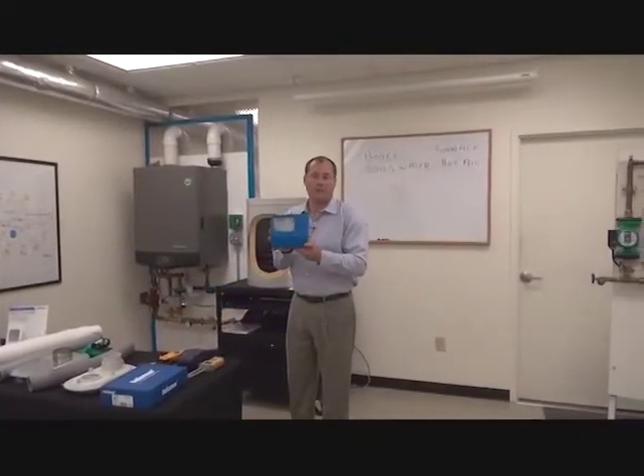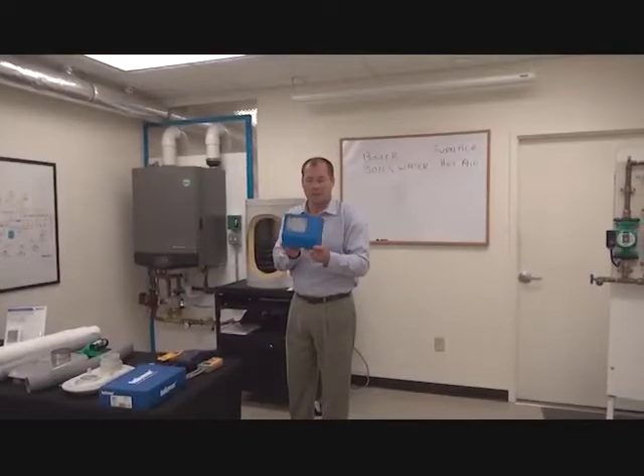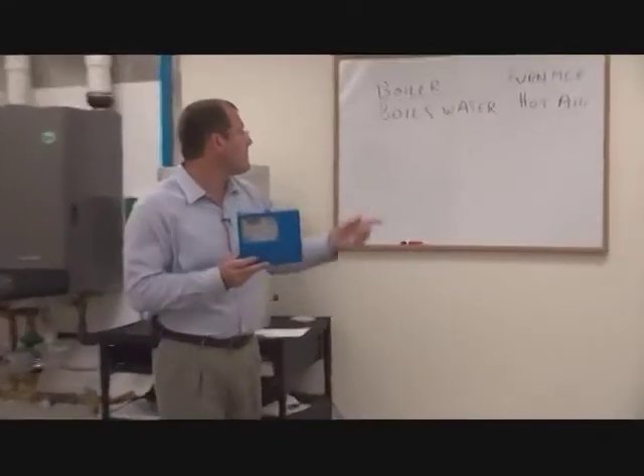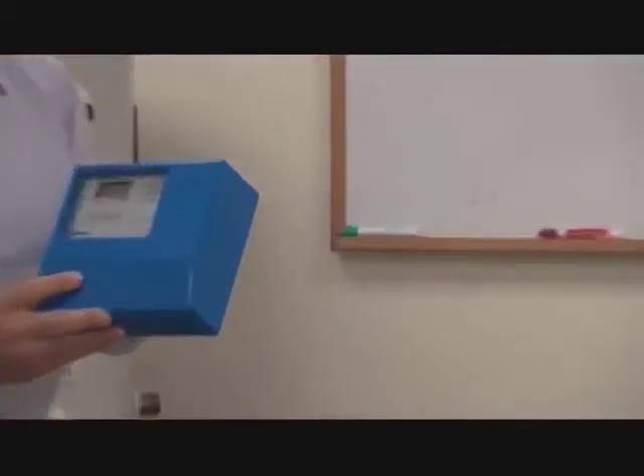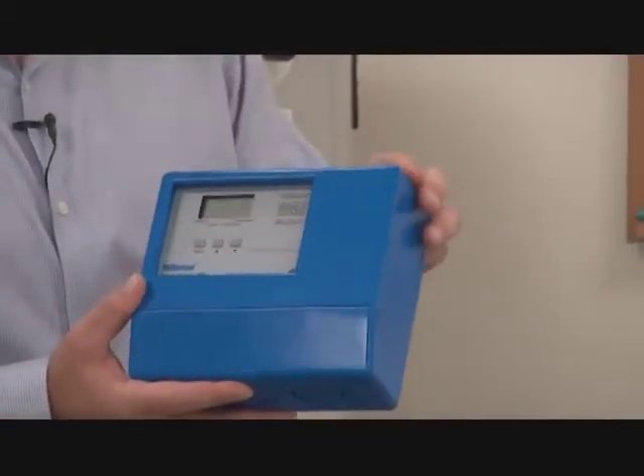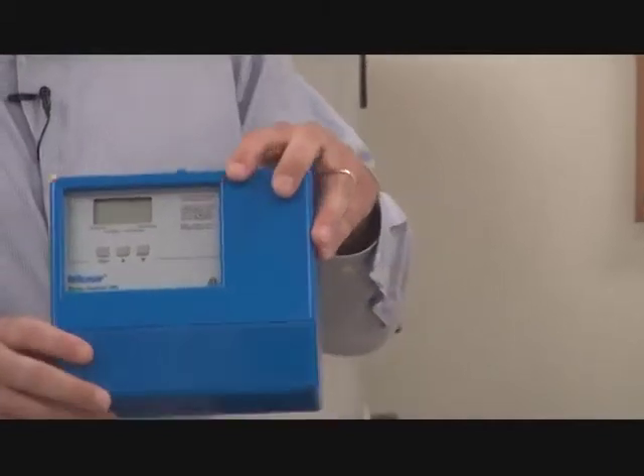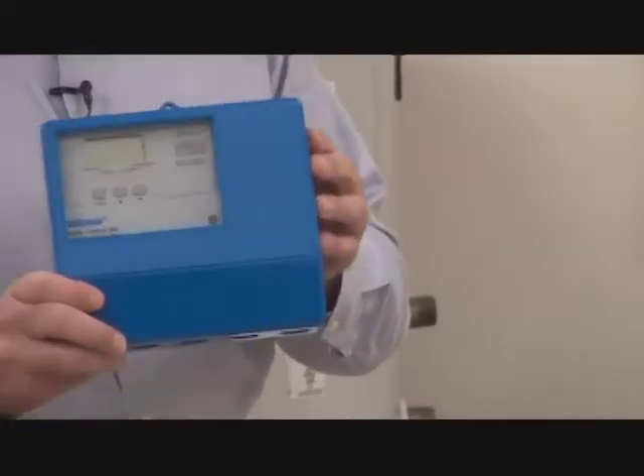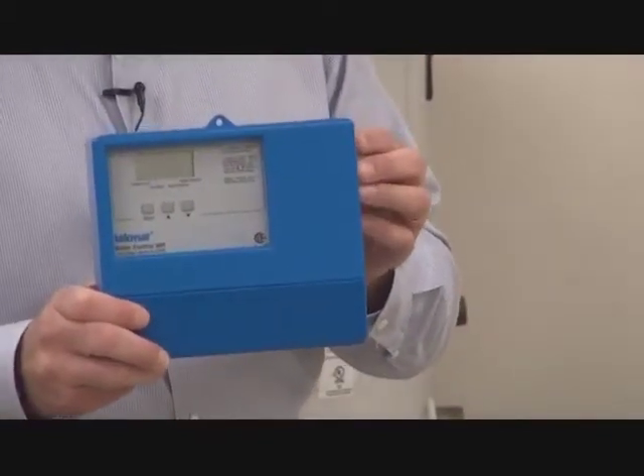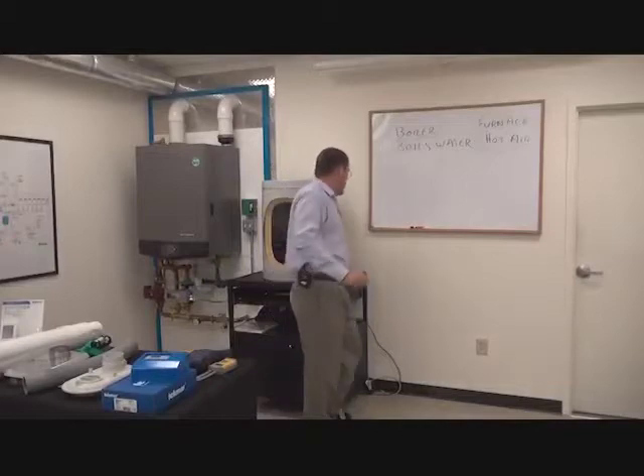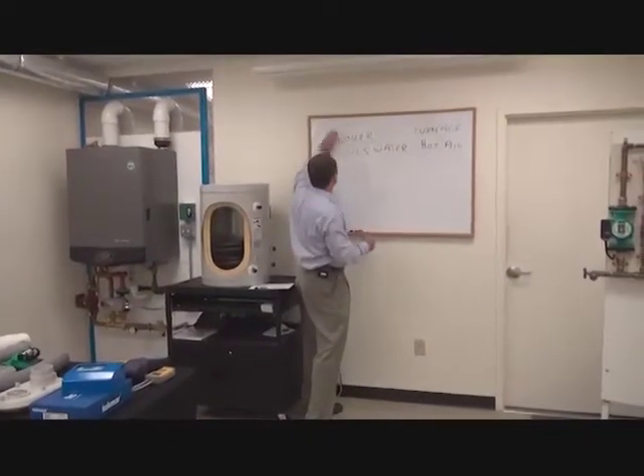This box can be added to any piece of heating equipment that heats water and its job is to pay attention to the outdoor temperature and to pay attention to the boiler water temperature and adjust that boiler water temperature based on how cold it is outside. It's very simple in terms of what it does, but I'll show you how it affects efficiency.